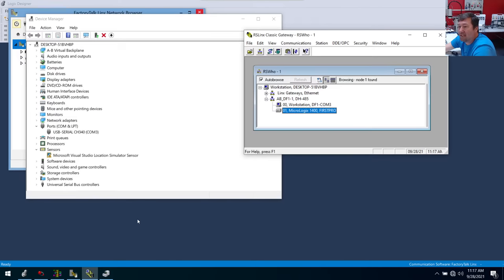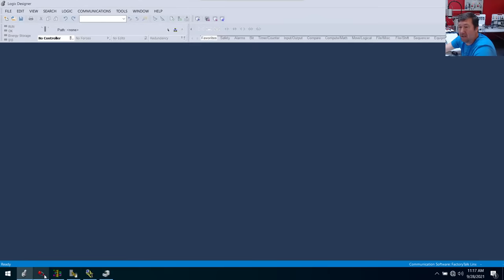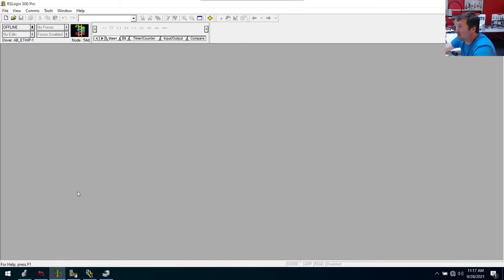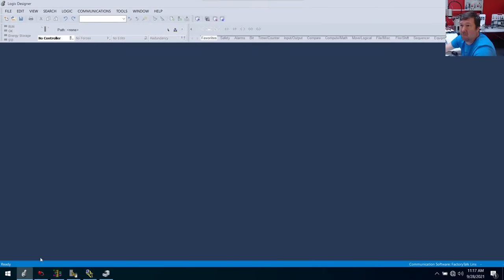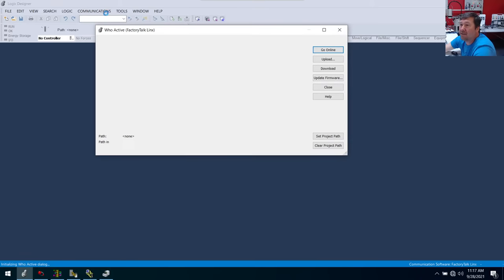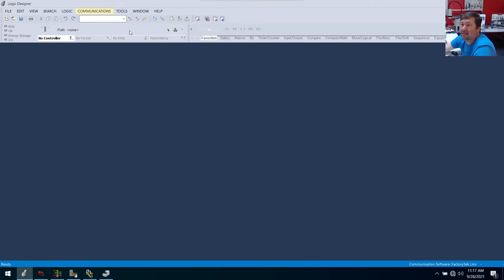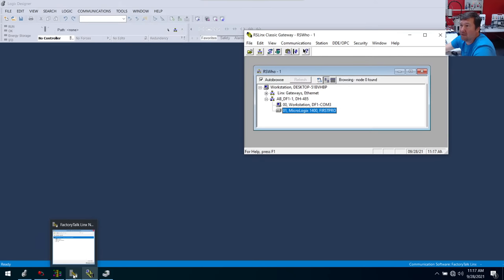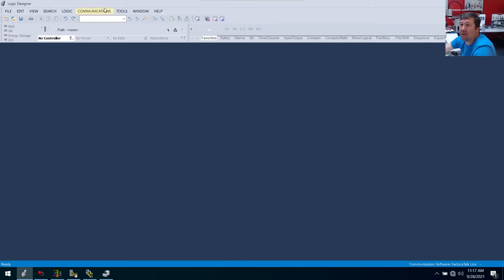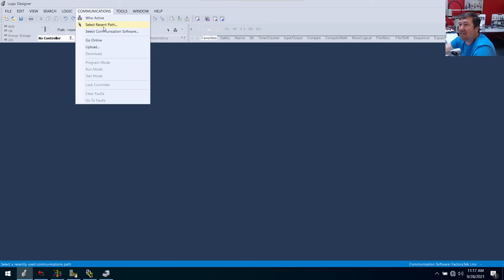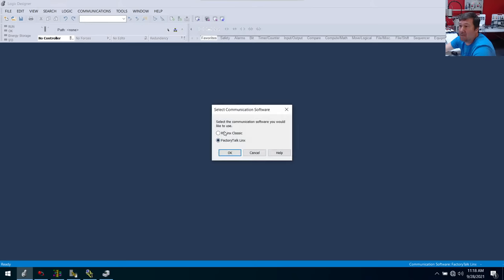Now we need to know what software to connect to. We already have three open: Logix Designer, Connected Components, and RSLogix 500. Well, RSLogix 500 — that's the software we're going to use. But just to show what would happen if we had the wrong one, we're going to go to Studio 5000. In Studio 5000, I always say go to Communications and then Who Active. I got to cancel this because I didn't talk about one thing: since we have two softwares here — the old RSLinx and the new FactoryTalk Linx — our newer software gives you the option of which one to use. If you're using Ethernet or USB, absolutely use the FactoryTalk Linx. But right now we're going to go over serial, so we're going to select RSLinx Classic.